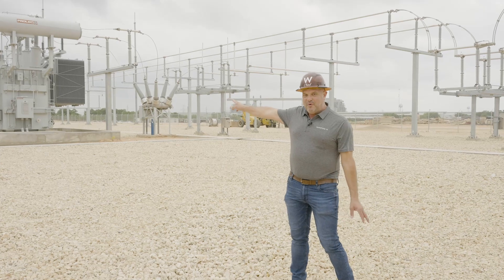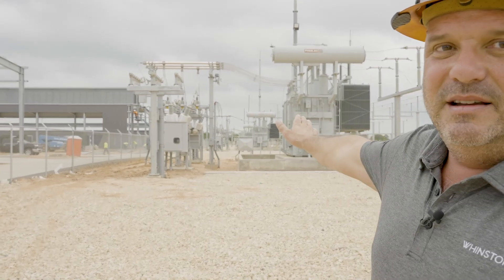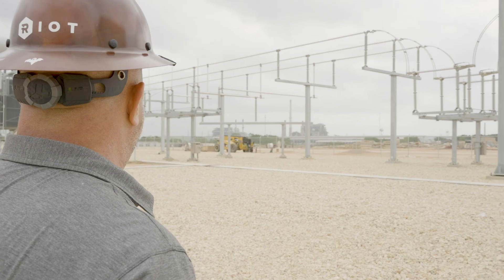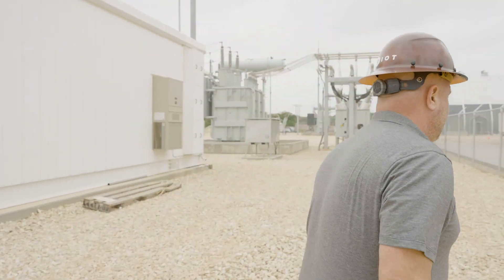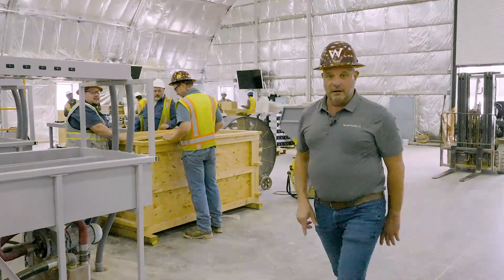We're inside a 700-megawatt substation. Looking straight through to the end, we have a 100-megawatt transformer in the front as a spinning reserve, and then 700 more megawatts built in — each building has 100 megawatts attached to it. You can see our continuous bus and one of our cranes. Right next to our PDC, everything runs our smart response software, which controls our load. In the event ERCOT needs power, it turns our miners off and sheds that load back into the grid to help with stability.